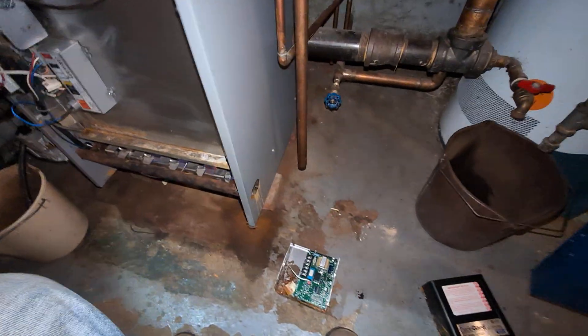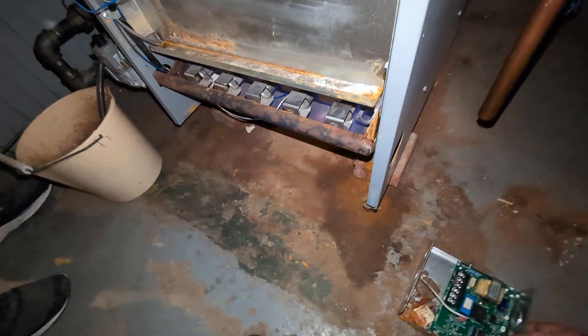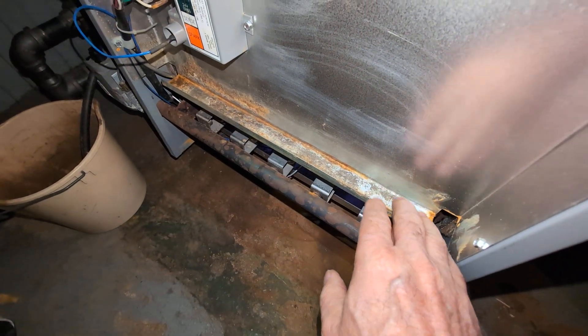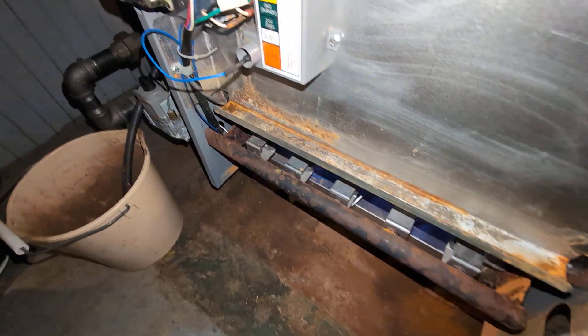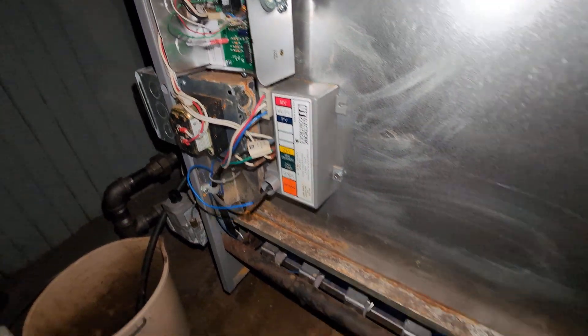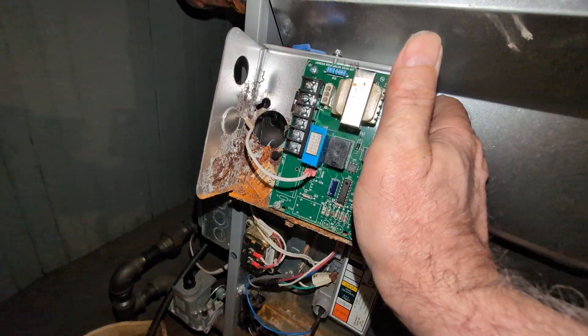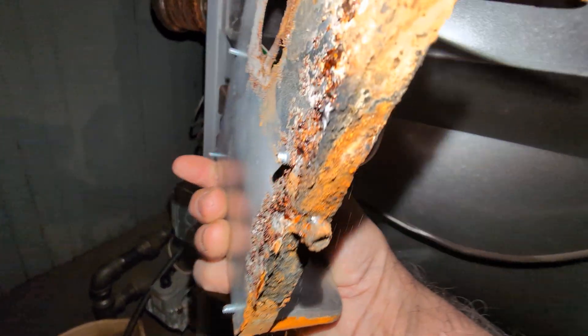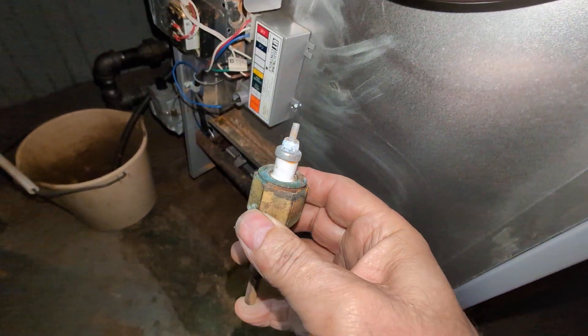On this particular model the cover is in front and you really can't see anything, so when you see water on the floor you have to take it seriously. I took the cover off and discovered there was a lot of water in this channel. When I restored the water level there was still water moving in the channel. I cleared out the water and noticed there was a little water drippage up there. Once I removed the cover you can see there was definitely a lot of water, and it appears the water was coming from the probe itself.